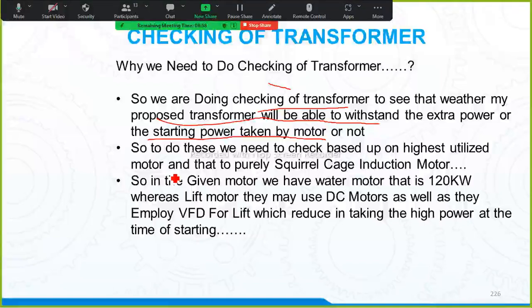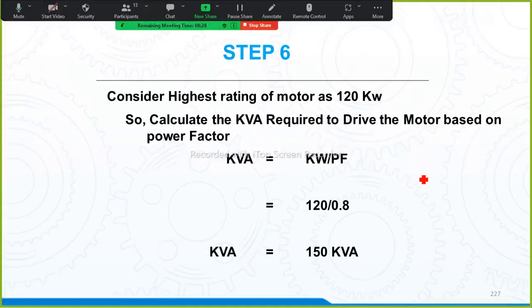Now you might ask, sir, why are you not taking firefighting? Firefighting motors are also there, but they are not used 24/7. Only whenever there is a fire accident are they used. So I'm going to check purely the water motor, which has to be switched on on a daily basis. I'm taking an example, 120 kilowatt is my total motor. But in reality, you will not have 120 kilowatt, because they will give a working motor separate and a standby motor separate. So when doing the checking, we need to check based upon the working motor only, not the standby motor. Now I got 120 kilowatt. So consider the highest rating of the motor is 120 kilowatt.